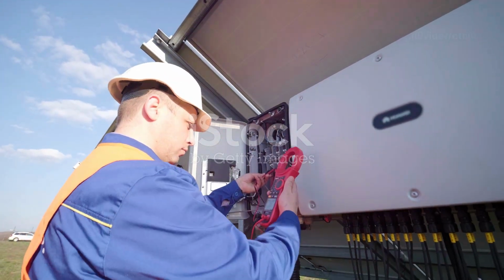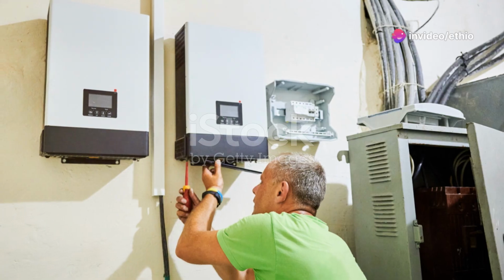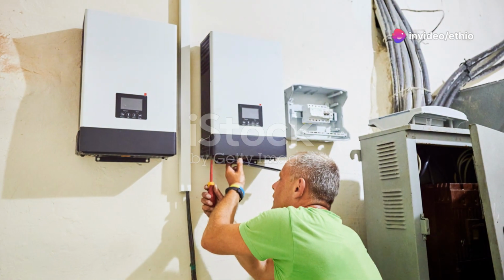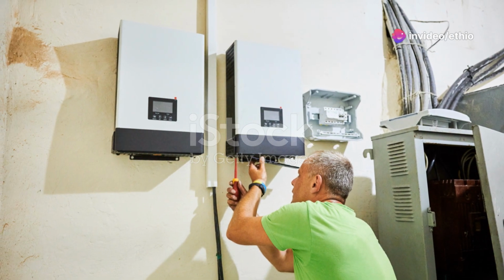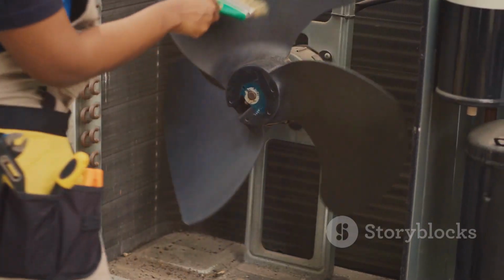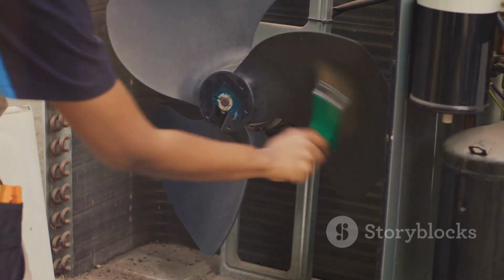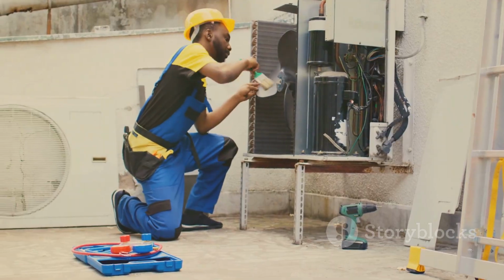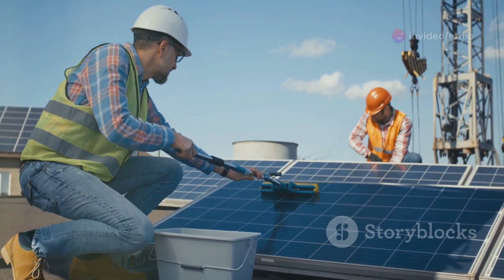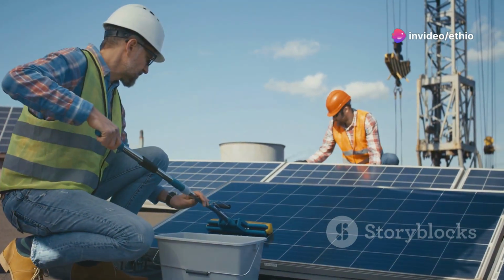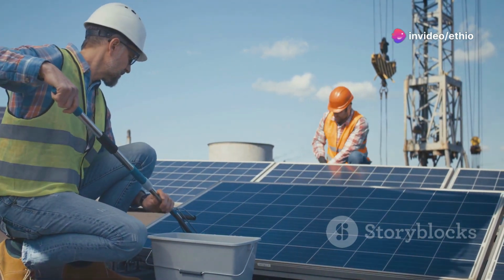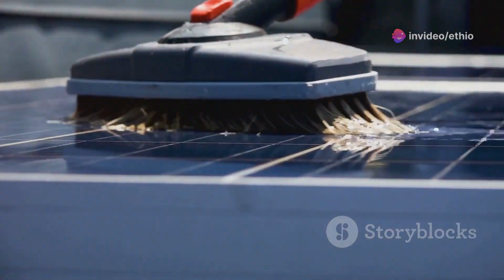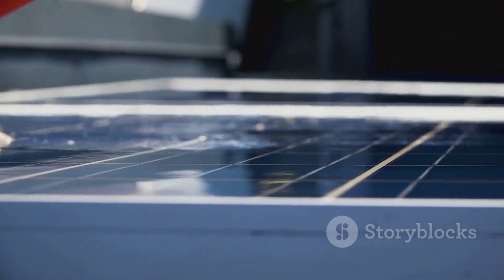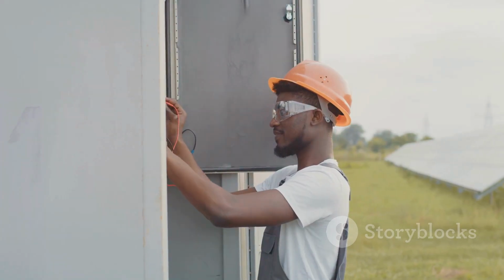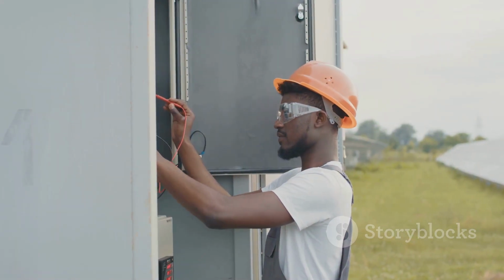If your inverter is hot, check its location. Is it in direct sunlight or a closed space? Good airflow is important. Clean the cooling fan and vents with a soft brush or air blower. Make sure nothing is blocking the airflow. For low efficiency, compare today's power output to past records. Clean your solar panels. Dust, leaves, or bird droppings can lower output. Check all cable connections. Loose wires can waste energy.